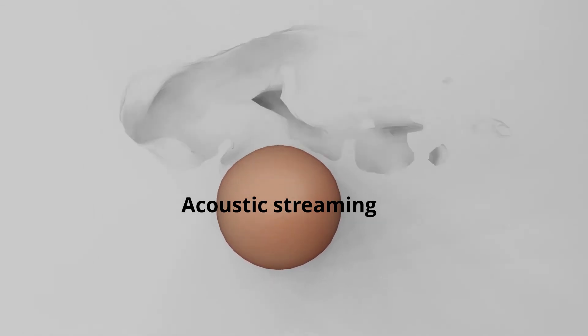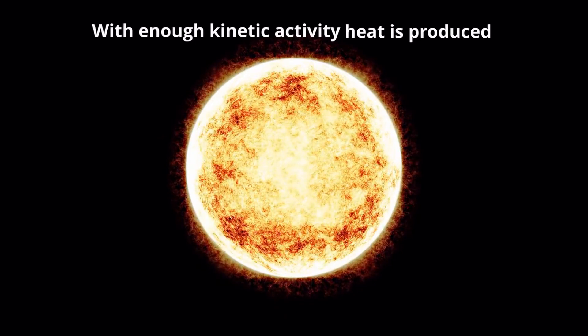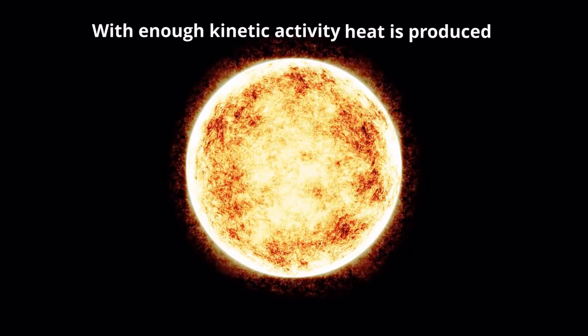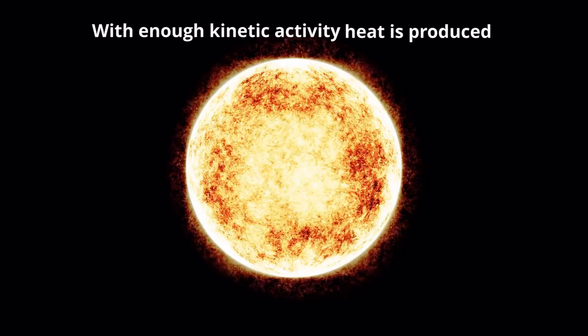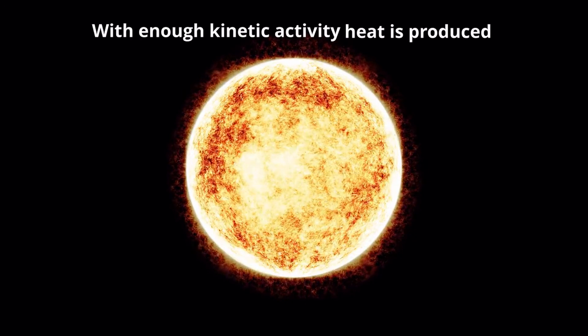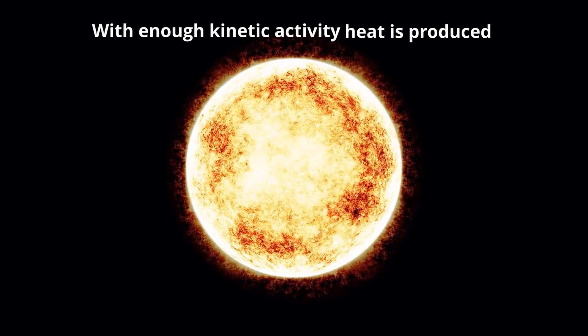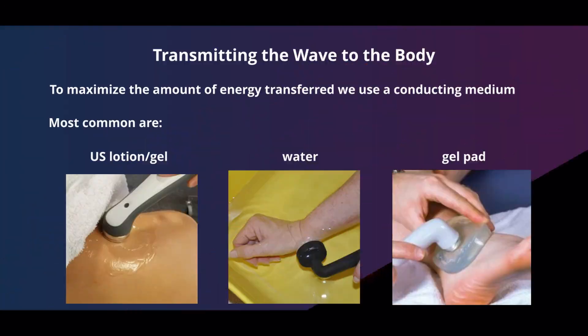Cavitation and acoustic streaming result in the non-thermal effects of ultrasound. Ultrasound also has thermal effects. The use of higher ultrasound energies can result in the transfer of thermal energy from the ultrasound head to the patient, which can provide therapeutic benefits as well. The transmission of ultrasound energy from the sound head to the patient is not a very efficient process. Therefore, we try to improve the efficiency by use of a conducting medium, most often ultrasound lotion or gel, water, or the use of a gel pad.